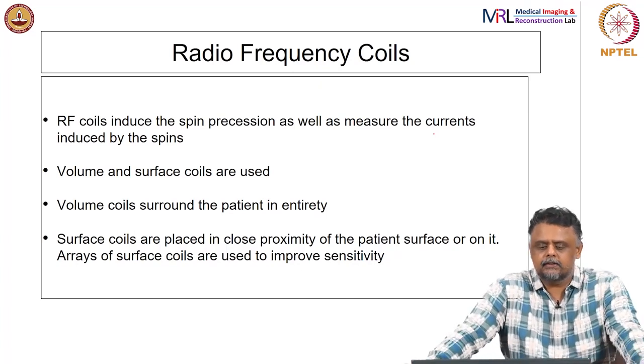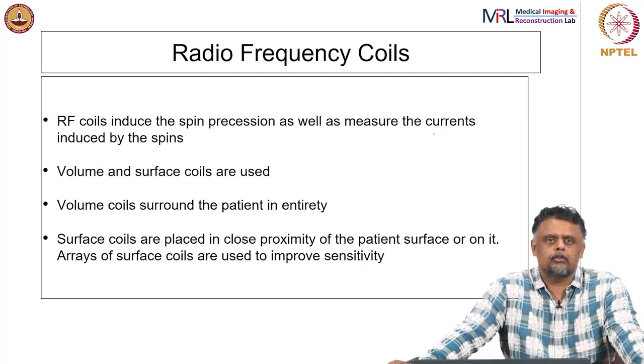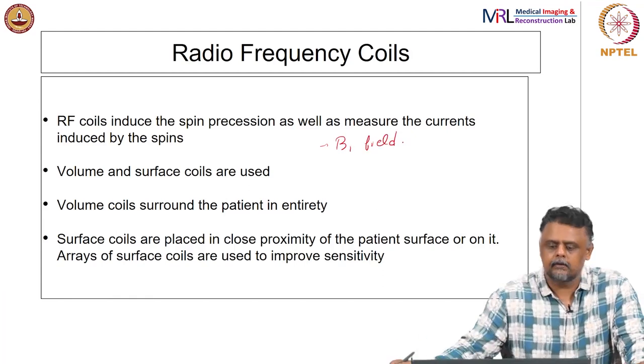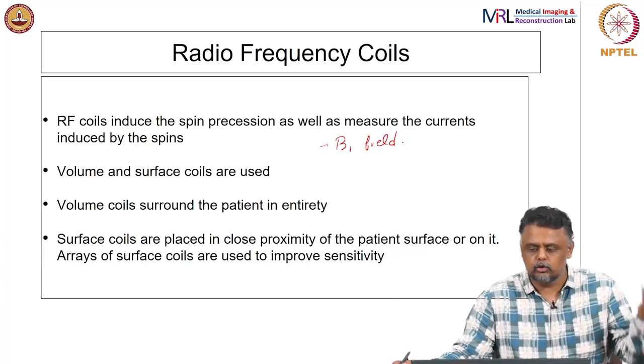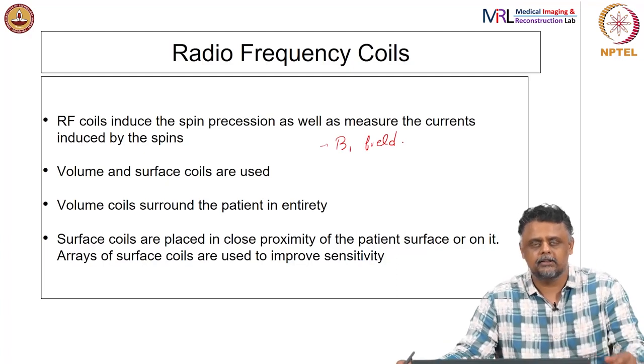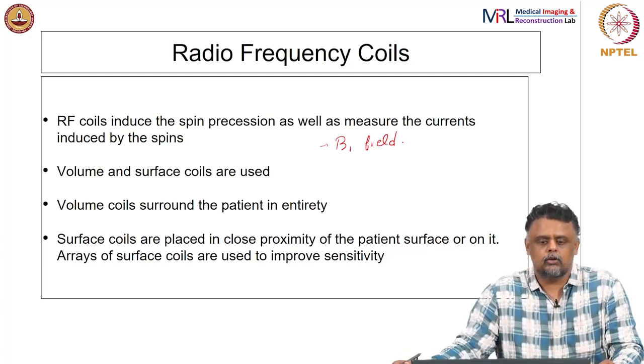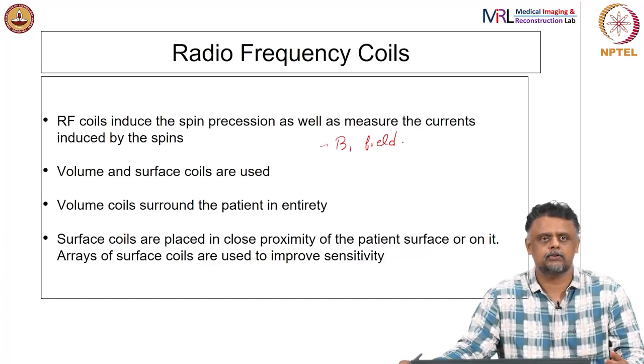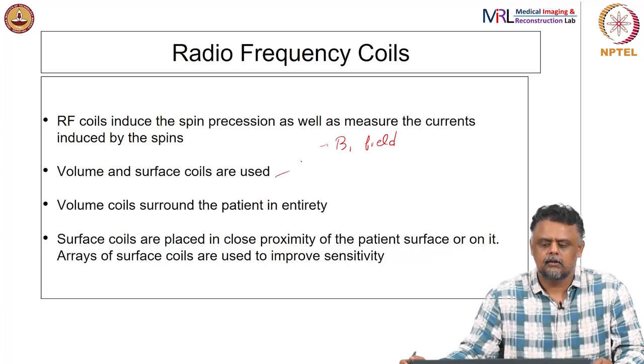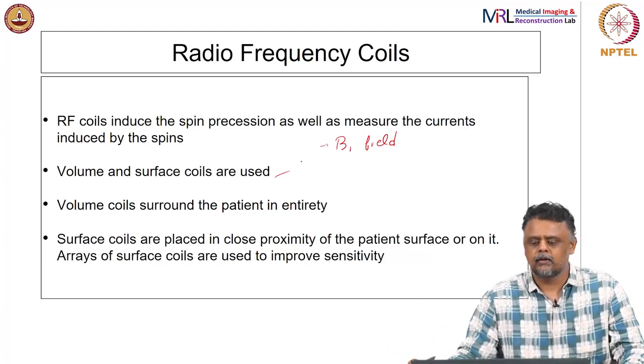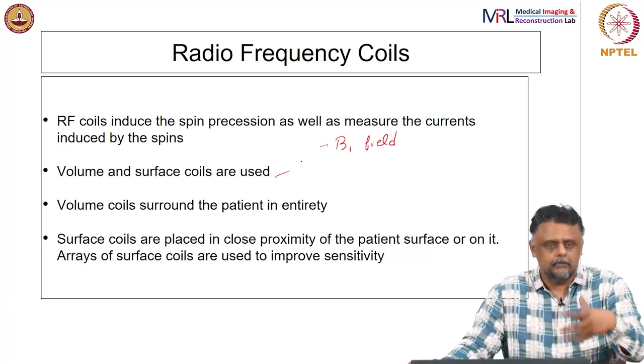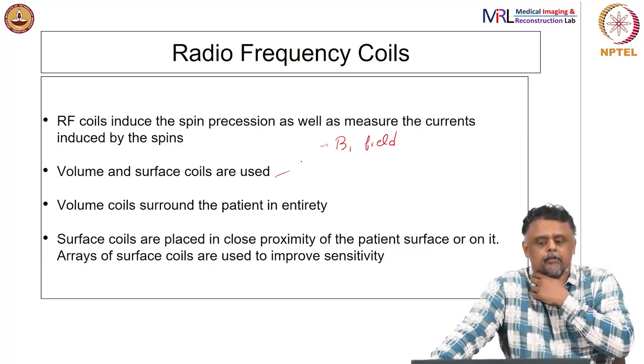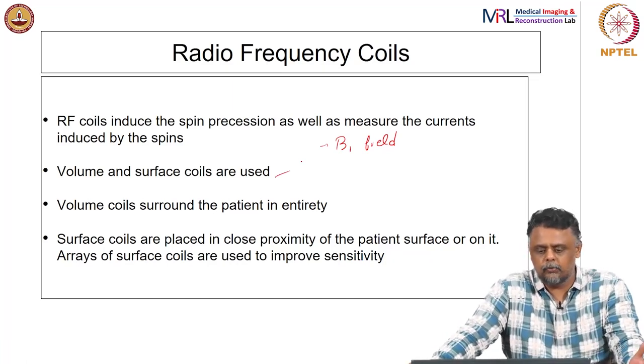The radio frequency coils produce the B1 field, which induces spin precession. These coils also measure the current induced by the spins. So the RF coils do both the excitation of the spins as well as the measurement — they act as both transmit and receive coils. There are volume coils which surround the patient and surface coils placed in close proximity to the patient. Designing these coils to get the correct RF field shape is itself a field of research.